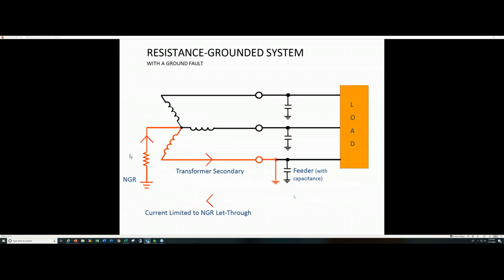Well, let's talk about a resistance grounding system. Now, remember we talked earlier about engineering controls, what can we do? Well, what if we were to take the Y of the transformer and just put a ground there, just like we did, but also add a resistor? So we're going to limit that fault current, should a feeder go to ground and come up through the resistor and go back to the Y. We're going to limit that.